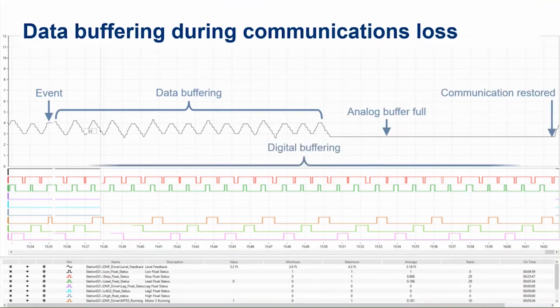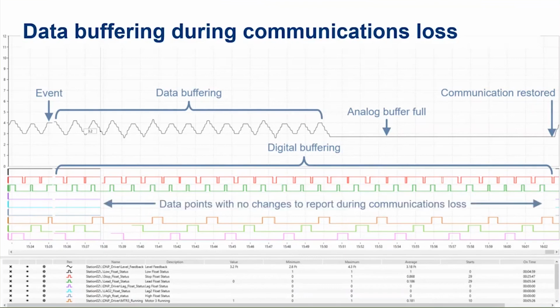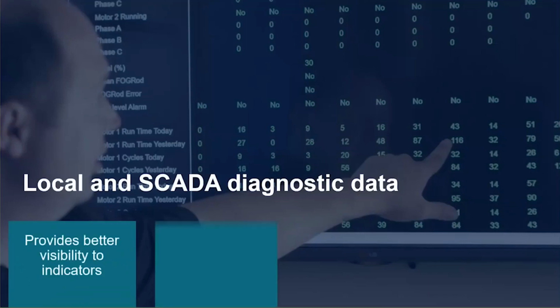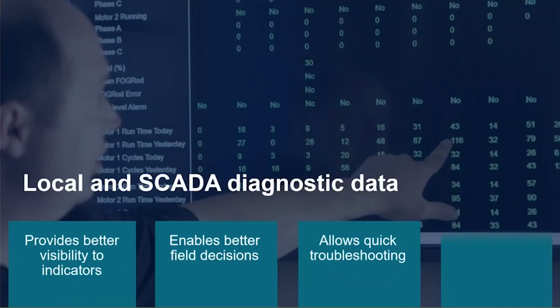Now, the digital buffer is a lot larger, and so you'll notice we didn't lose any digital data at all. What we were able to record here is every start, every stop, every float tip, every virtual float tip. If you have an analog transducer, you have virtual float tips, down to the exact millisecond, so you don't lose any of that troubleshooting that you want to do. What it does is it allows you to use your SCADA system and the data that you're collecting to make better field decisions, even if you have not a very reliable communication infrastructure.